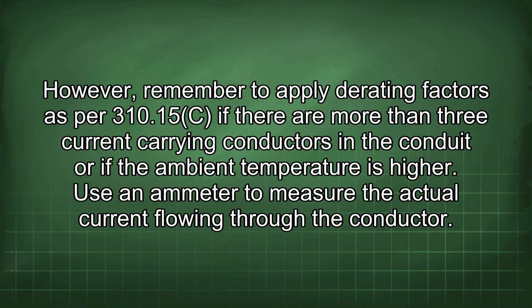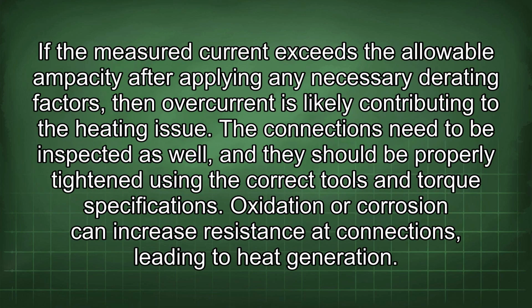However, remember to apply derating factors as per 310.15(C) if there are more than 3 current-carrying conductors in the conduit or if the ambient temperature is higher. Use an ammeter to measure the actual current flowing through the conductor. If the measured current exceeds the allowable ampacity after applying any necessary derating factors, then overcurrent is likely contributing to the heating issue. The connections need to be inspected as well, and they should be properly tightened using the correct tools and torque specifications. Oxidation or corrosion can increase resistance at connections, leading to heat generation.